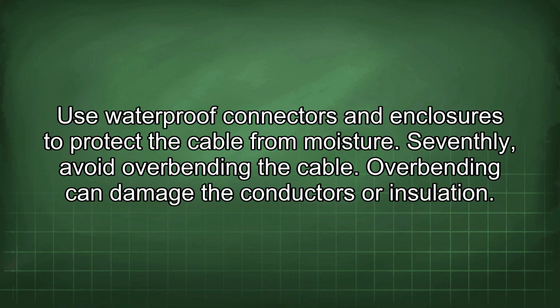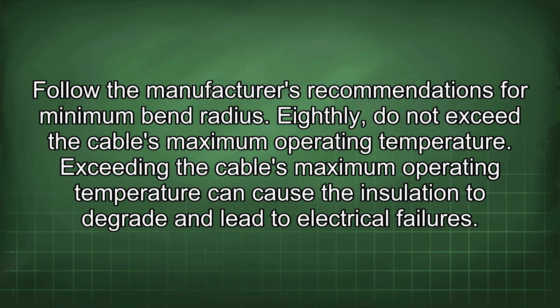Seventhly, avoid overbending the cable. Overbending can damage the conductors or insulation. Follow the manufacturer's recommendations for minimum bend radius. Eighthly, do not exceed the cable's maximum operating temperature. Exceeding the cable's maximum operating temperature can cause the insulation to degrade and lead to electrical failures.